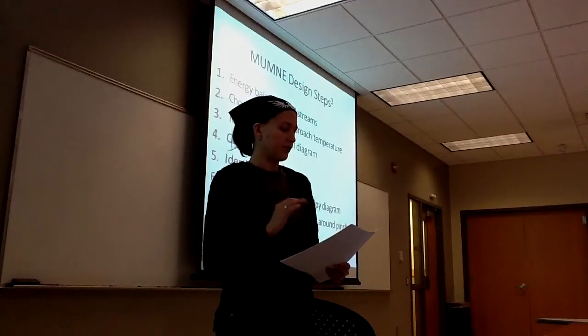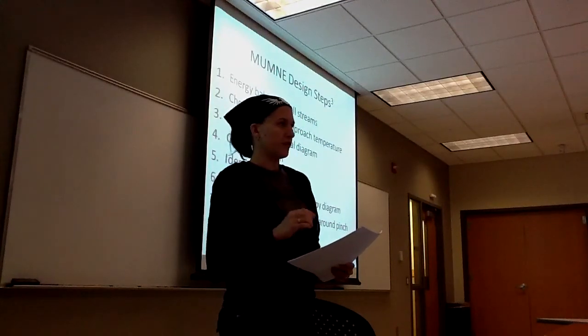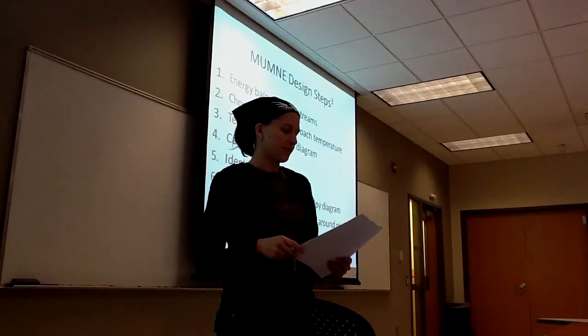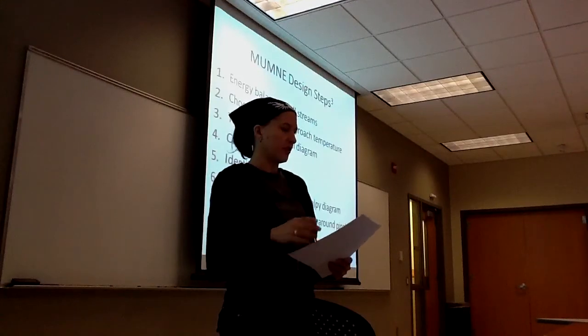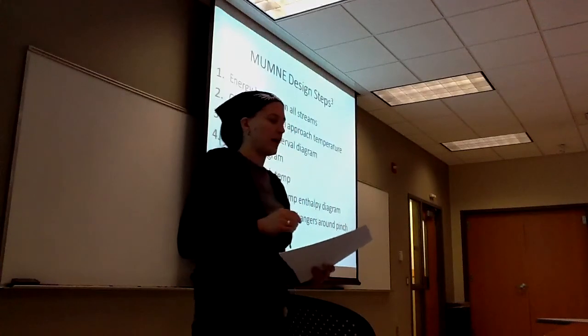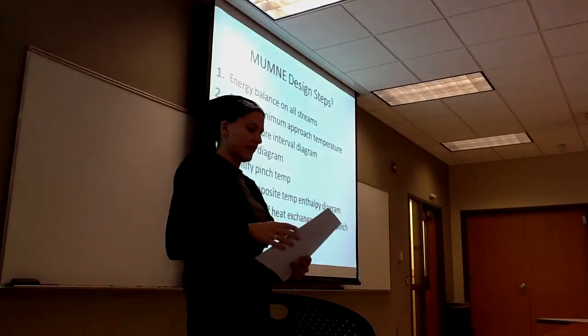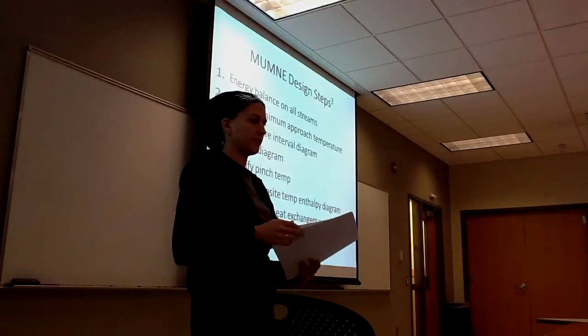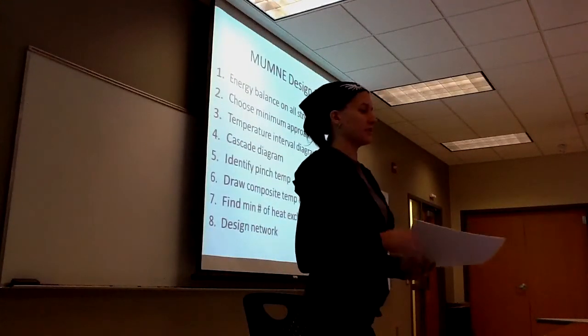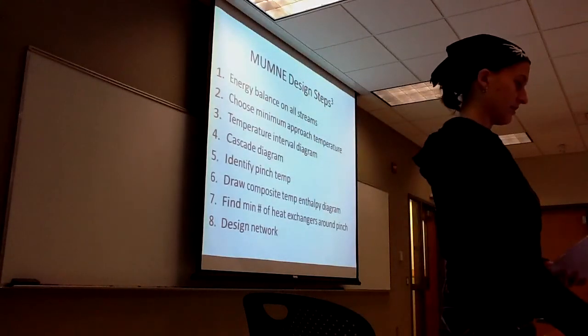Then you have to do number three: draw each stream, label it, calculate the heat flow at each interval. Number four, take the energy excess or deficit and calculate it for each interval on the temperature interval diagram. The cascade diagram shows you the minimum hot and cold utility requirements. Number six is a temperature and enthalpy diagram for the entire process. Number seven is finding the minimum number of heat exchangers that you need above and below the pinch. And finally, you get to design the whole network of heat exchangers.